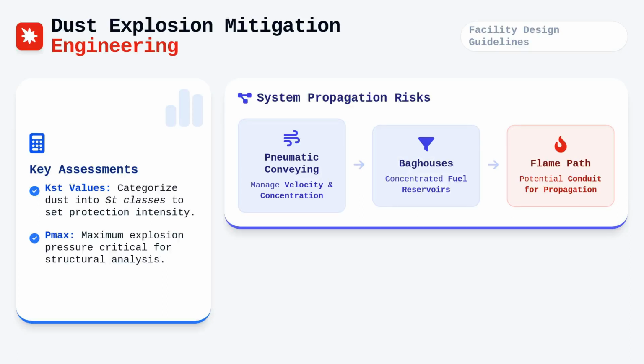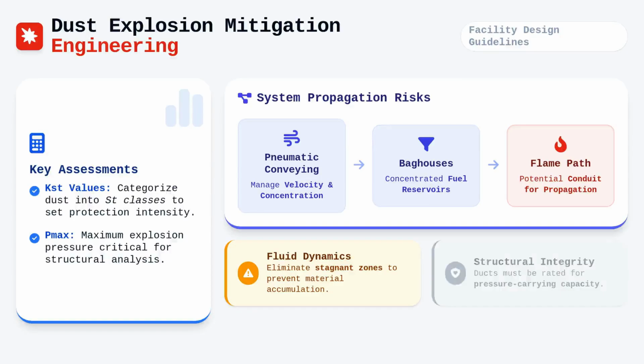Dust collection topologies, particularly baghouses, function as concentrated reservoirs for hazardous concentrations of fuel, and the fluid dynamics within these units must be balanced to prevent stagnant zones where material can accumulate. A failure to recognize the pressure carrying capacity of these ducts often leads to structural failure during an internal event.